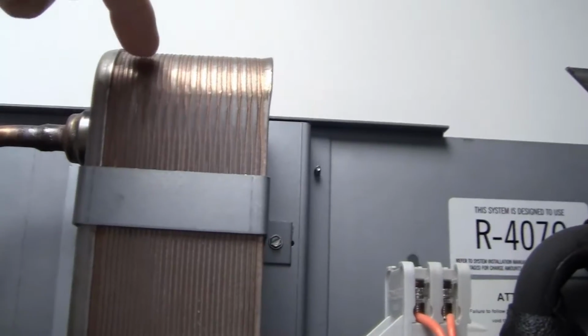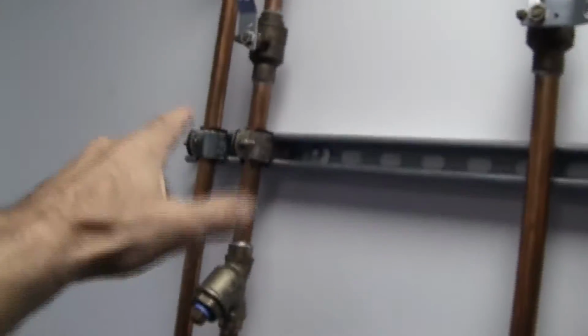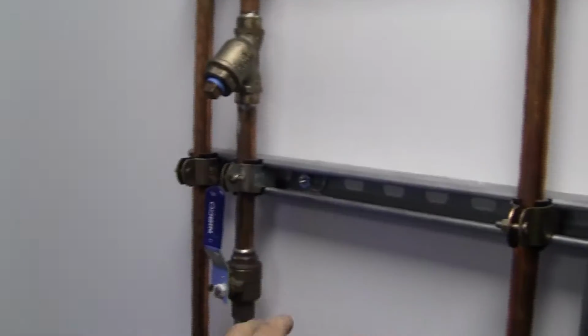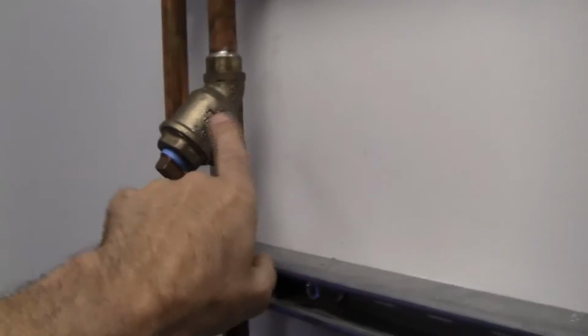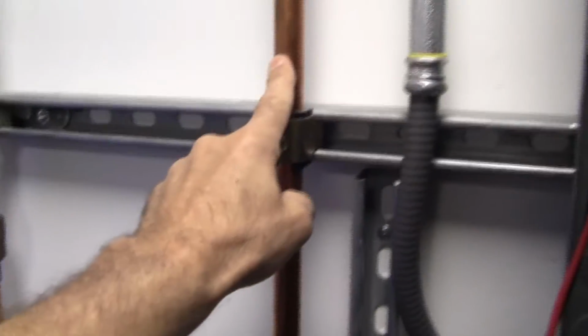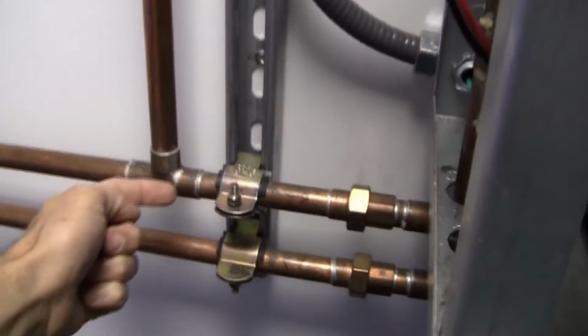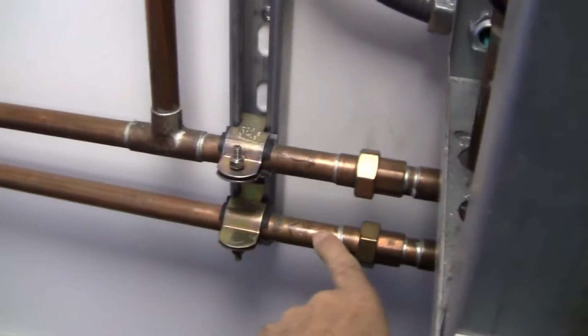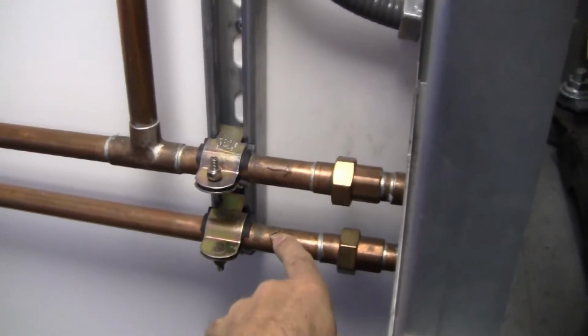Water-cooled condenser. Okay, so there is your condenser right there. This portion that I'm putting my finger on right there, that's the condenser, and it's water-cooled. These are your copper water pipes, and you can tell by the directional arrow and by the strainer direction that the flow of water comes down here. This is a bypass line right here. There's your shutoff valve if you needed to bypass, which we don't. So normally your water goes into the unit cold and it comes back as the heat is being rejected from the room through this pipe here, and it goes out into a water chiller at the cooling tower at the top of the rooftop somewhere.